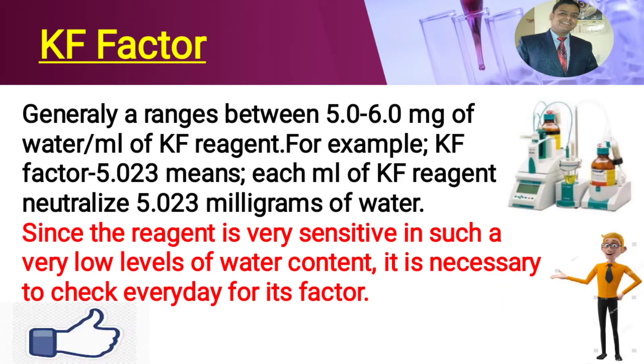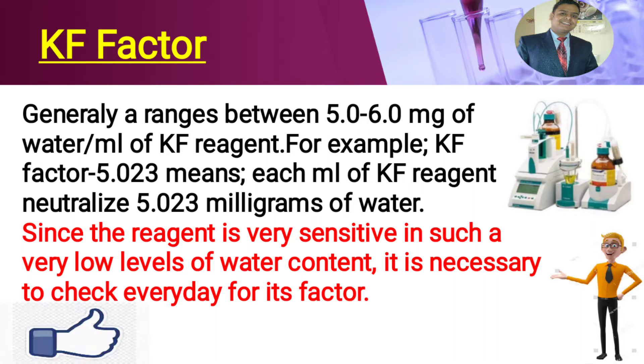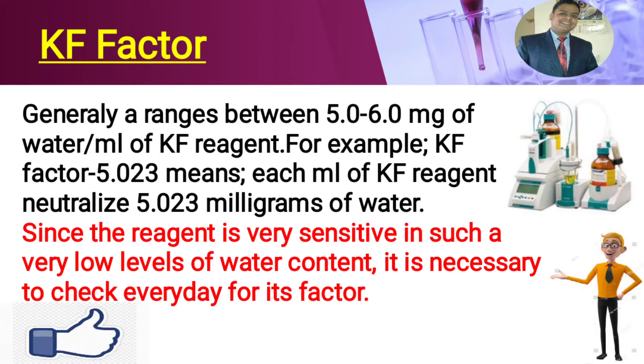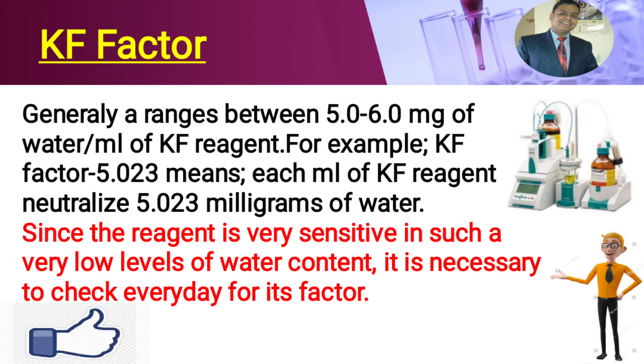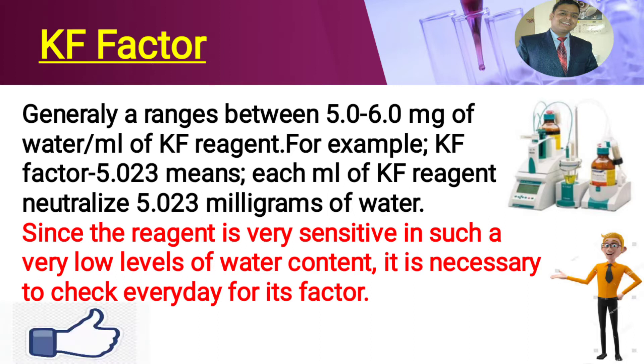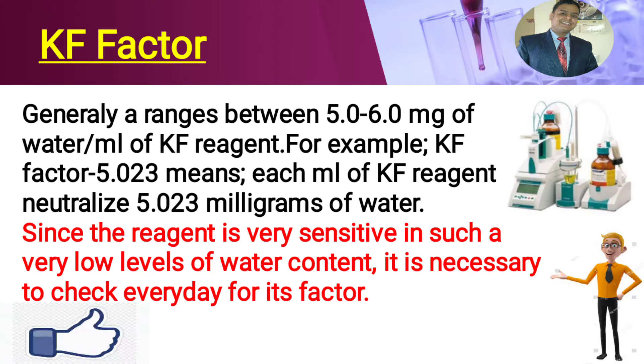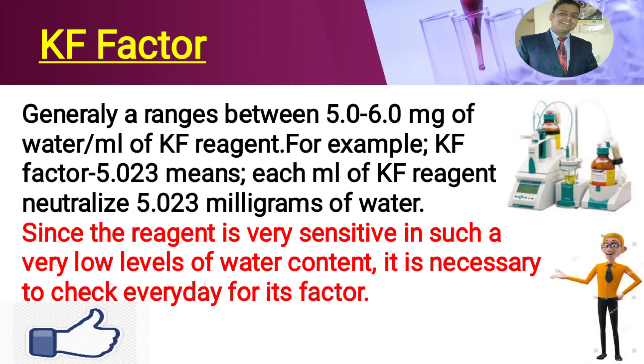Generally, the range of Karl Fischer reagent is between 5.0 and 6 mg of water per ml of KF reagent. For example, if we have the factor 5.023, it means 1 ml of Karl Fischer reagent neutralizes approximately 5 mg of water. As this reagent is very sensitive at very low levels of water content, it is very necessary to check it every day.